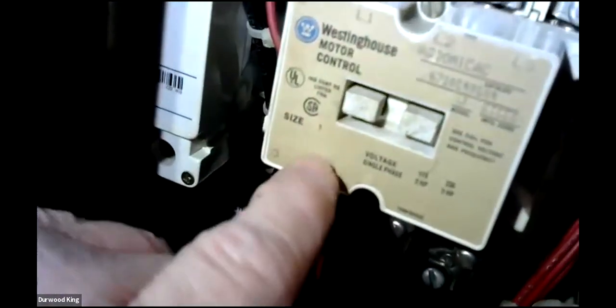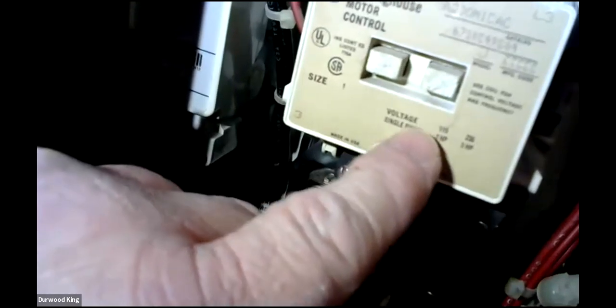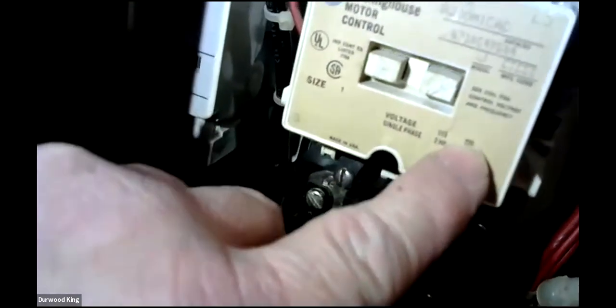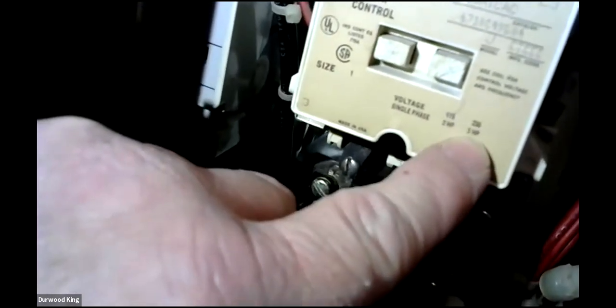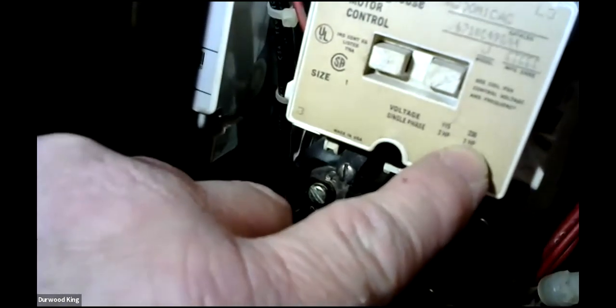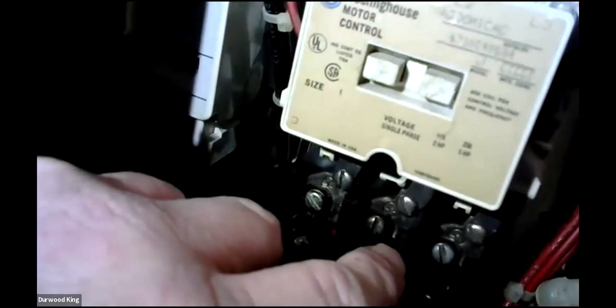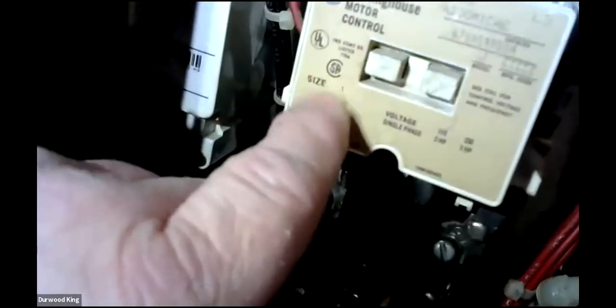So I'm going in. This is actually a NEMA. What size NEMA is that? Can you read that? Size 1. It's a NEMA 1, and it can run 115 volt or 230 volt at 3 horsepower. 3 horsepower at 230 volt. Okay, so that's where your NEMA numbers are, and you see physically how big of a starter that is. It's pretty good size, so your starter is actually bolted into your overloads.